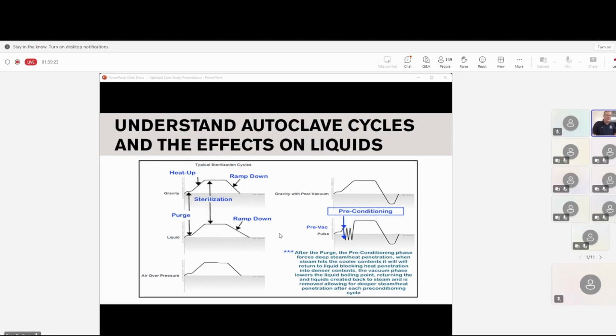So let's talk about the ramp down here real quick, and especially with the effects of liquids. If you look at the gravity, it's exactly what it does. At the end of the sterilization, it cuts off the steam to it, and then it says we're going to open up the drain valve and an air inlet valve. So it uses gravity to go down. So within 30 seconds to a minute, it's going to come back down to atmospheric.